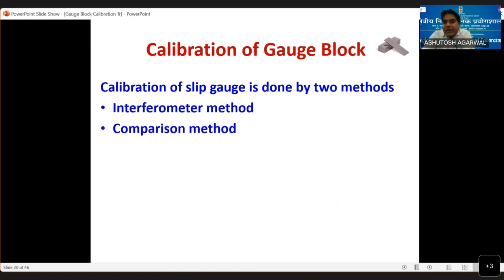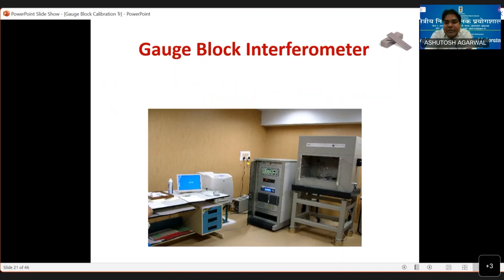So, calibration of gauges. How do we calibrate this gauge block? One is by the interferometric method, one is by the comparison method. So we have in NPL the gauge block interferometer, GBI 100. We have two lasers here, green and red. Red we calibrate with our helium neon, and green we send to the UK. And this is the area where we keep our gauge block. The interferometric method will give the interference pattern.